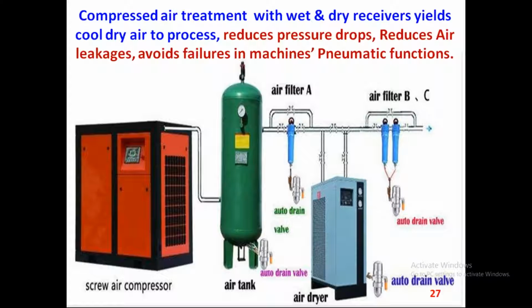So when the air is compressed through an air compressor, the water has to be removed in stages. If the water is not removed, then it will kill the pneumatic health of the given process. The pneumatic functions will malfunction because of water ingress into the air system. So we have to remove water in the post air cooler, in the air receiver, across the filters, the coalescent filters or water separator filters, and then in the refrigerant dryer. If water is removed at all these stages, the pneumatic health of the system will be excellent for a given industry.